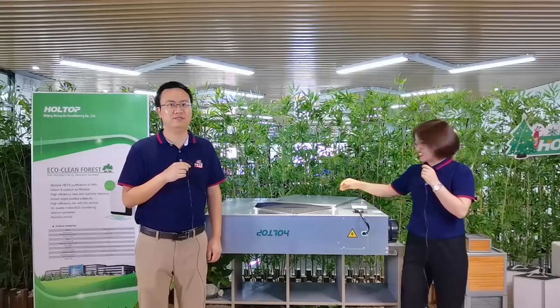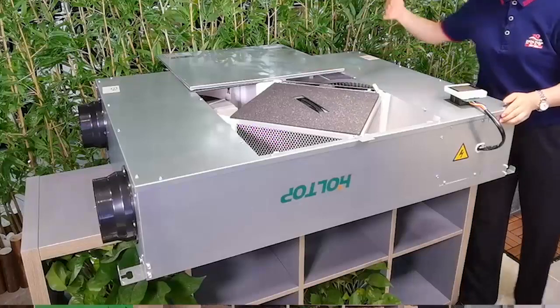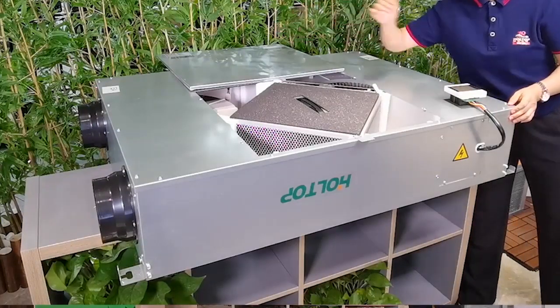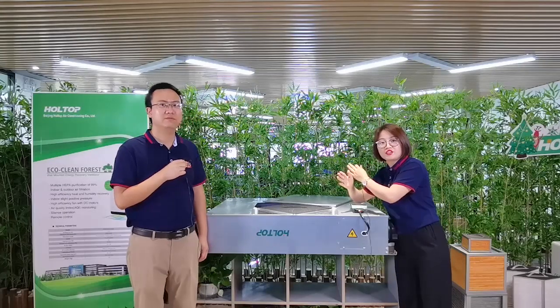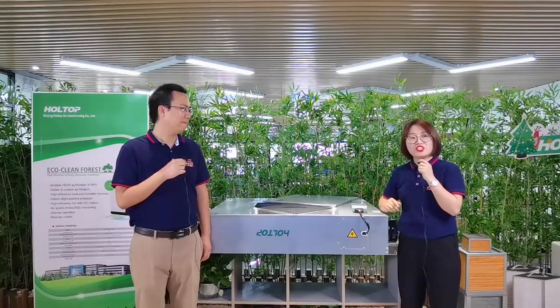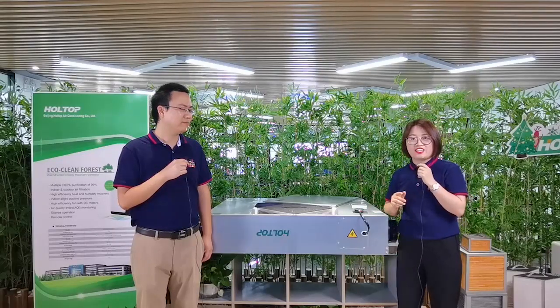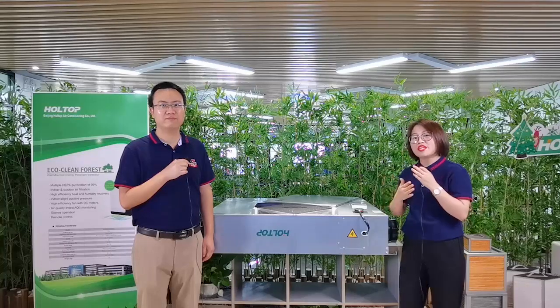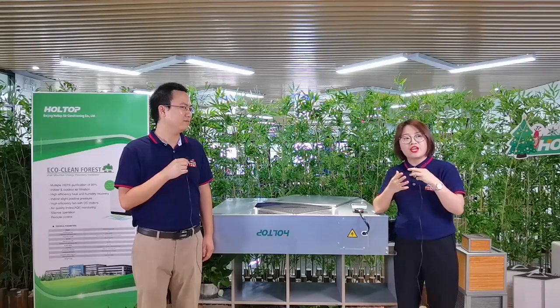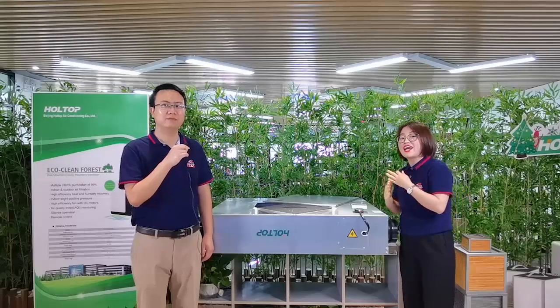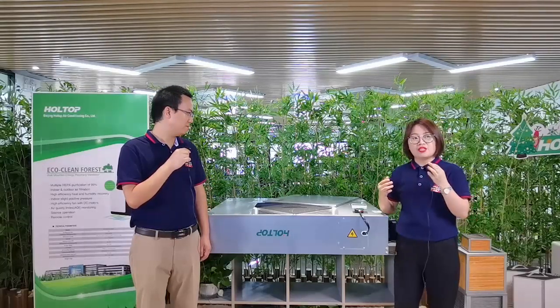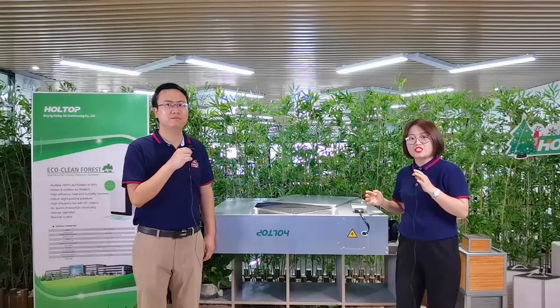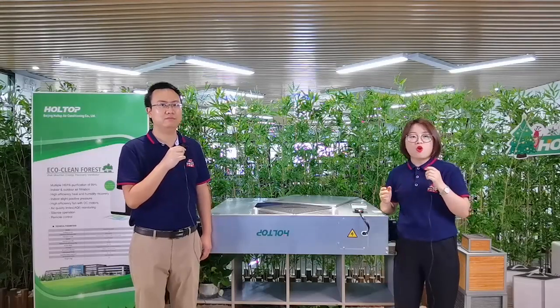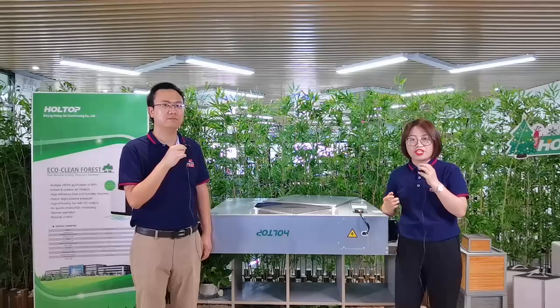Yes, sure. This is the outdoor air, the supply air, return air, and exhaust air. The two air streams cross — the fresh air and exhaust air come across with a temperature and humidity difference. The heat can be exchanged from the warm air to the cold air, and moisture can be transferred from the wet air to the dry air, without them touching. So the energy and heat can be recovered, and it is balanced ventilation to save energy and balance heat and humidity within a building. This all helps create a clean, healthy, and comfortable indoor air quality.